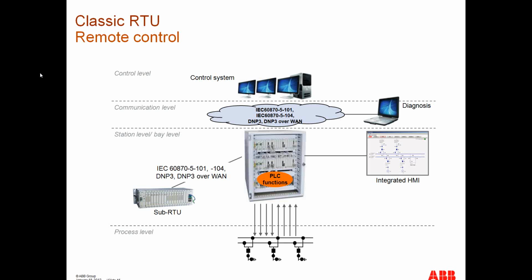So what do we see? Beginning at the process level at the lower end, different measurements and signals and stuff like this come out of the process level going into the RTU. So the RTU collects the data as well as sends commands or data to different devices in the process level, for example circuit breakers.